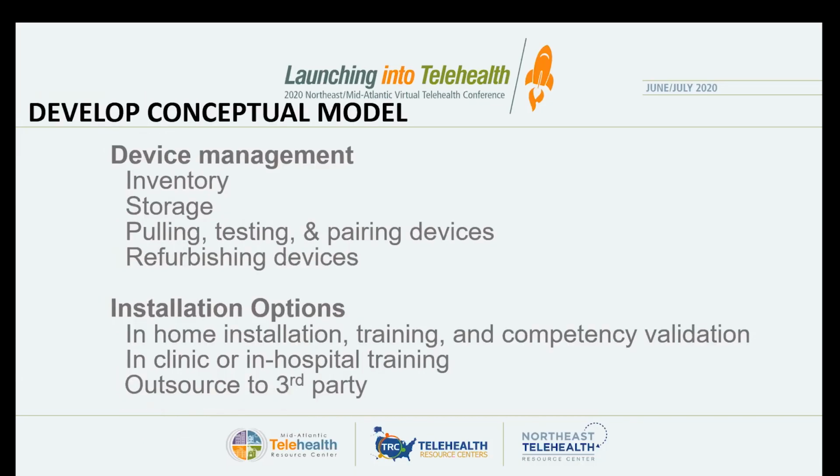Now, most importantly is to develop your conceptual model. When I talk about conceptual models, I'm talking about device management, installation, de-installation options, as well as the monitoring. So when you start a program, you need to determine internally how the devices are going to be managed. Who is going to receive that inventory? Where is it going to be stored? You're going to need a clean location to have that equipment stored.